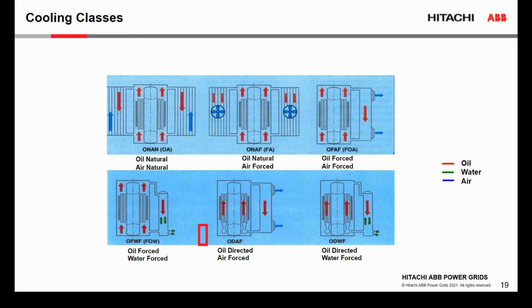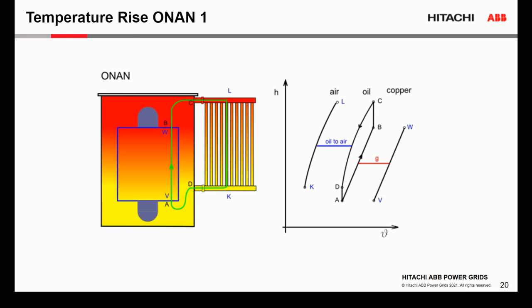Now we will go more into the details for each particular cooling solution, and we can see that we can combine radiators with the pumps and also coolers with radiators. Radiators with the pumps and fans with the radiators and pumps. So, as I said, ON cooling with radiators is very common on the smaller transformers. We use only natural circulation of oil and also around the transformer, natural air circulation.